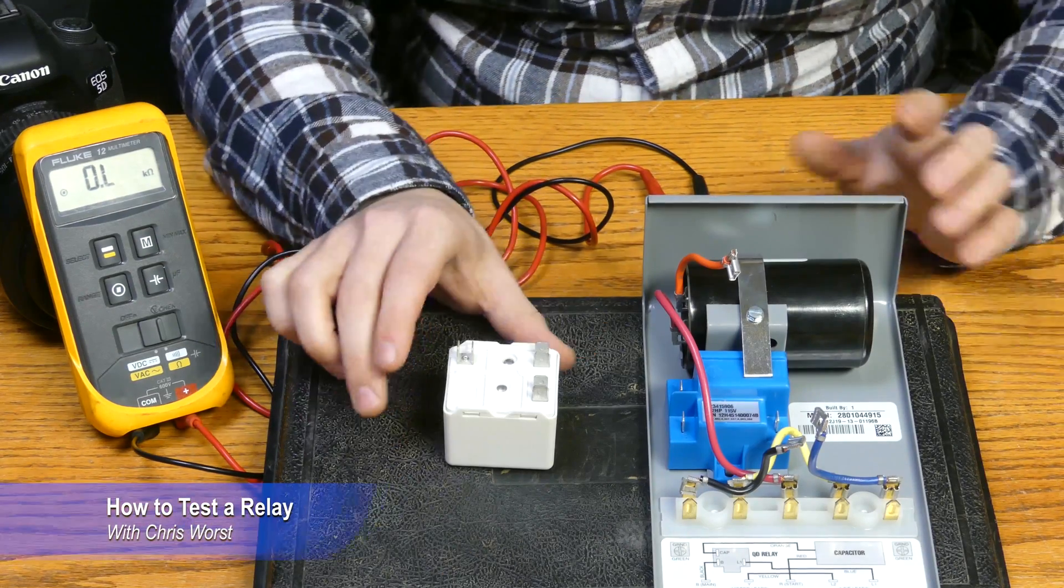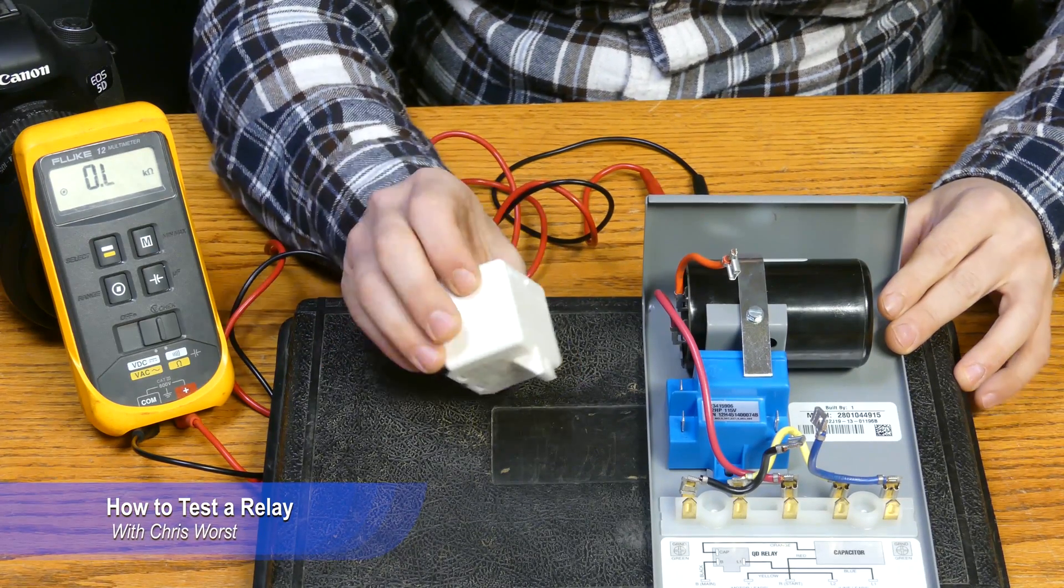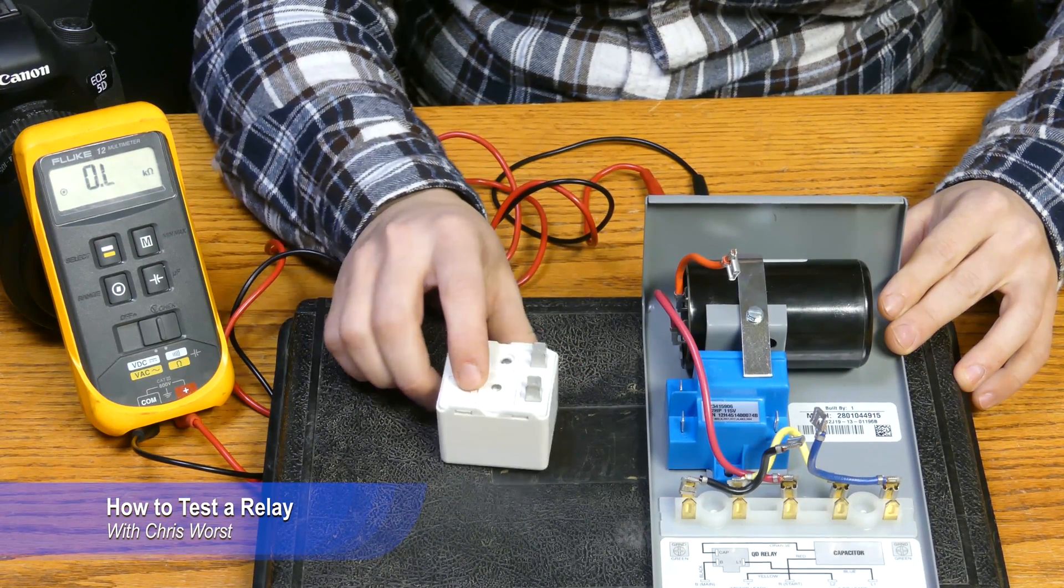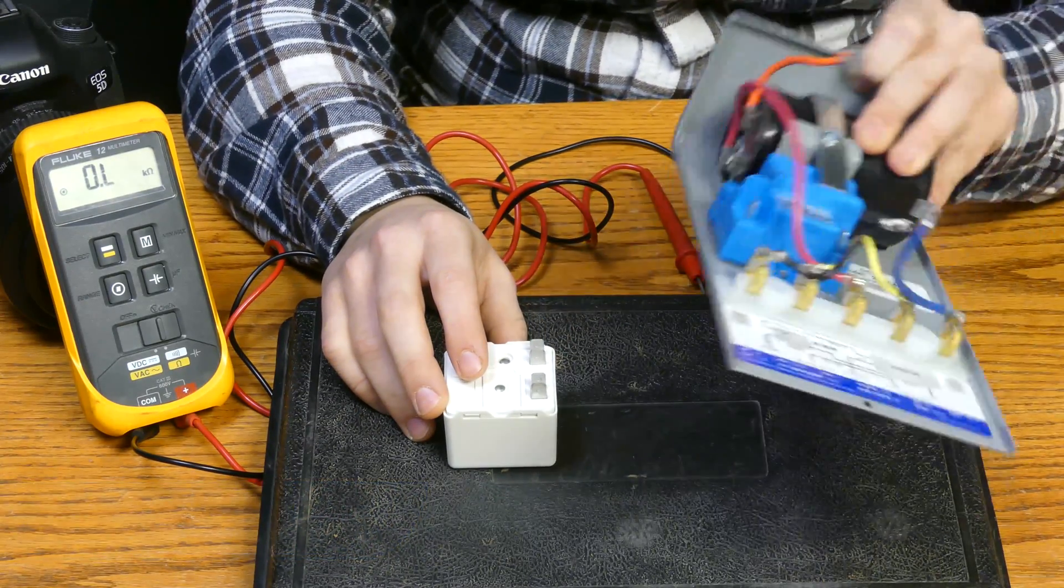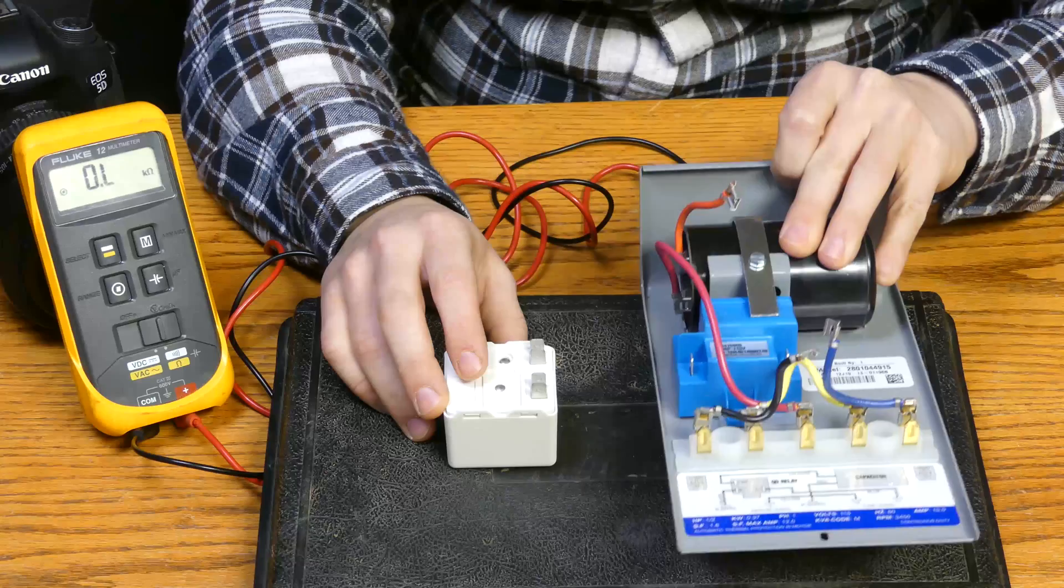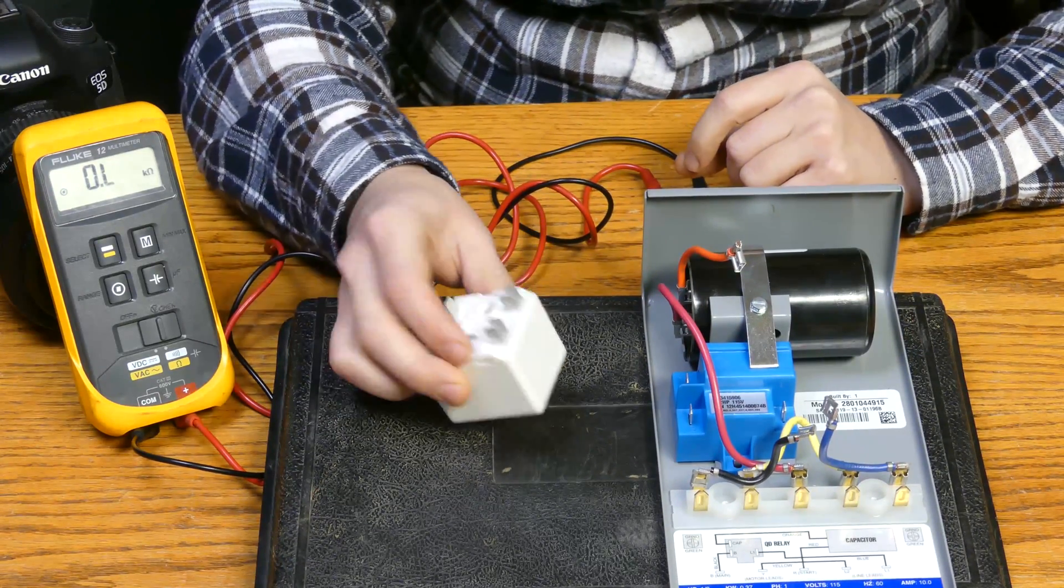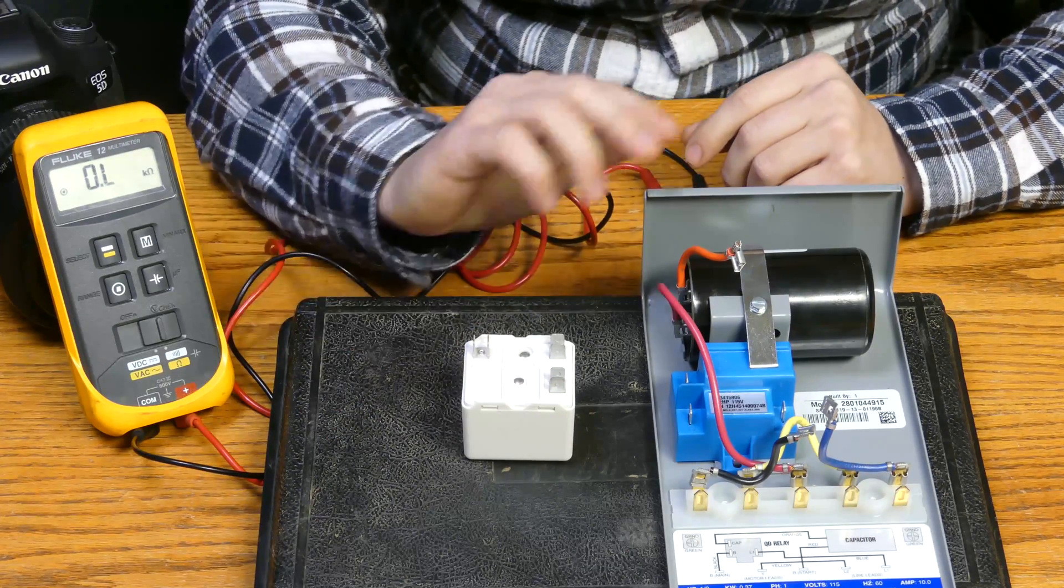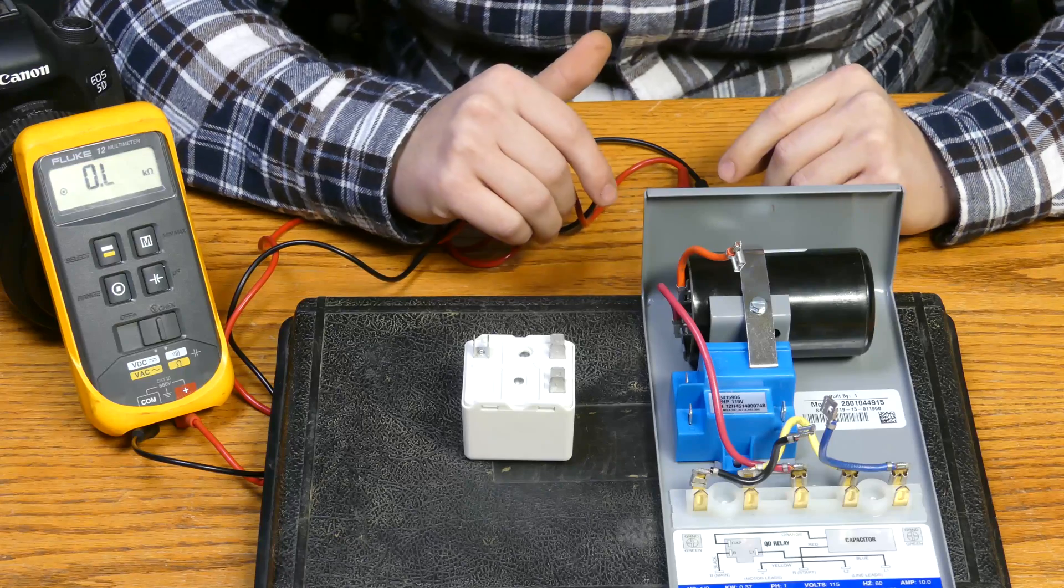Okay, so we're just going to jump into today's video. We've got two different relays we're going to show you how to test depending on the horsepower of your motor. You might have the smaller QD style, so we've just got a QD control box here. We went ahead and pulled the leads off, or you might have one of these larger relays here. Actually, they're two completely different types of relays, so we're going to show you how to test both.